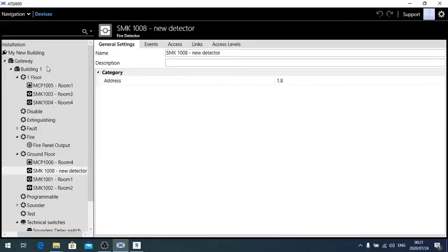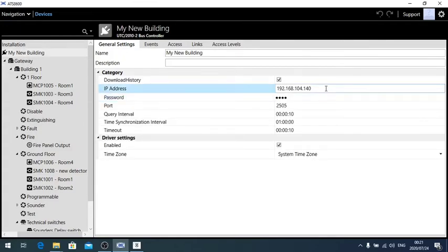This video was more to link the fire alarm panel. And as you've seen, we've imported it. And we've got the settings here for the gateway. The gateway is the first fire alarm panel on the network, which is being talked to via the Ethernet. That fire panel can be linked via fiber optics or copper RS485 to other fire panels, and they will be controlled via this main fire alarm panel.